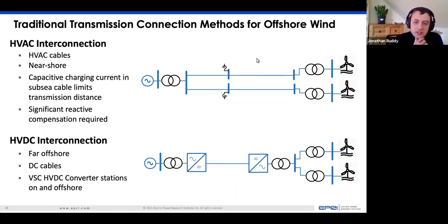So I'm just going to give a little context initially about the two main connection options for offshore wind: AC connections and DC connections. If we take the AC connection first, it's a direct connection to shore by a 60 hertz AC cable. You may have some offshore stations or offshore platforms in the middle with reactive compensation to extend that distance out. You do have things to consider onshore with reactive compensation because of the AC cables.